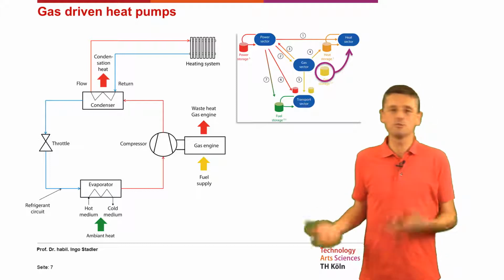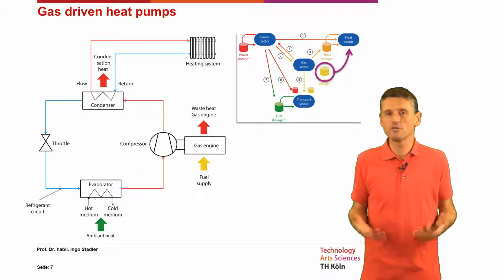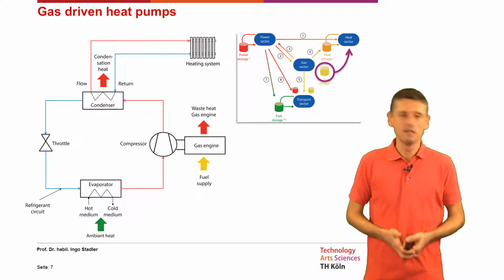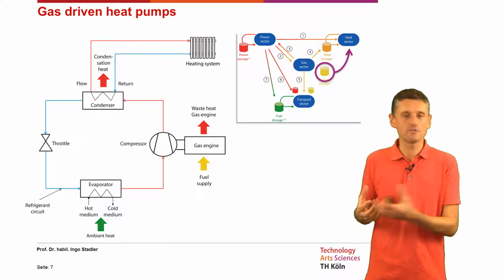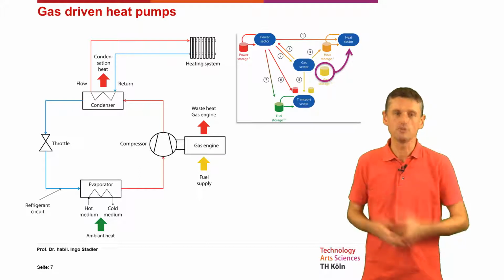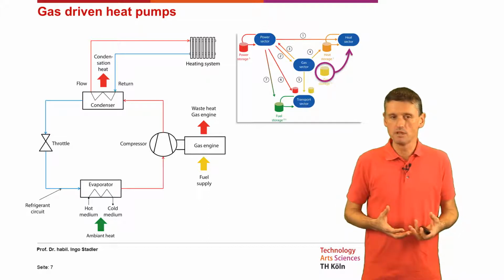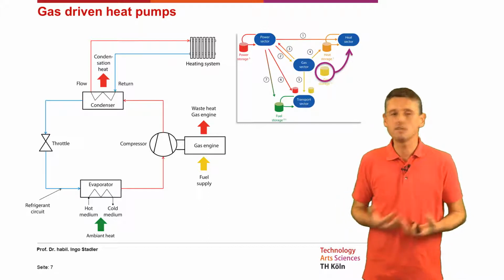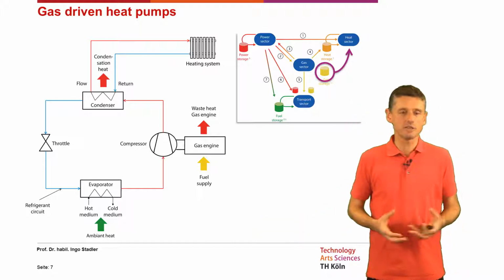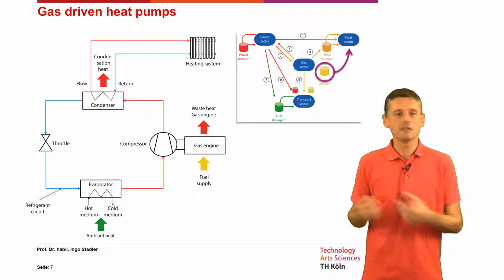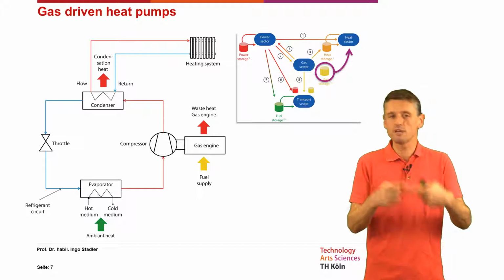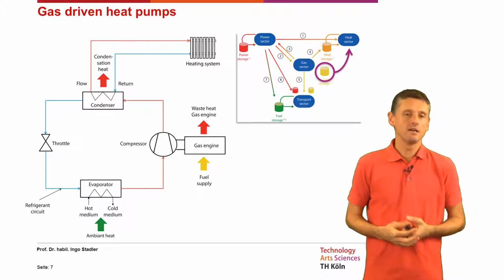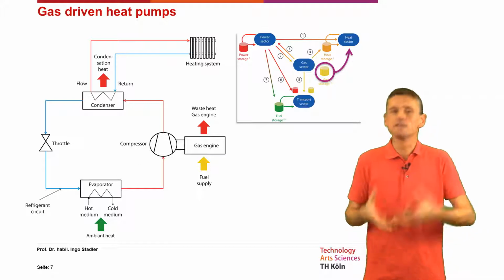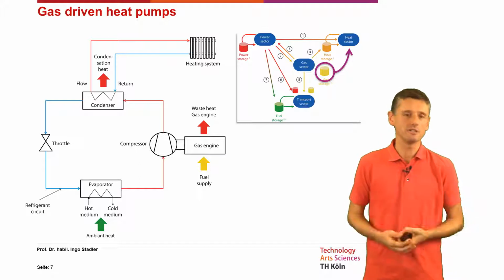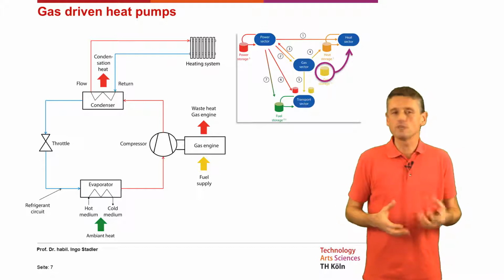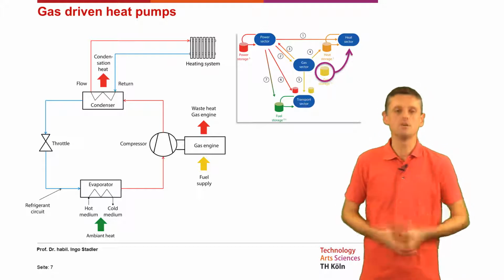Coming back to the heating sector, nowadays we operate a lot of electrically driven heat pumps, but we can substitute the electrical motor with a gas-driven motor to operate the compressor of a heat pump. Starting with the ambient heat in the evaporator, the gas motor compresses the evaporated cold medium, then in the condenser we gain that heat at high temperature, using it for the heating system before decompressing it in the throttle, closing the loop.